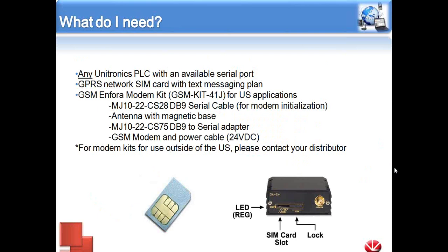So what do I need to do all this? This is going to work with actually any of our PLCs from the Jazz up. Jazz, M90, and all our Vision controllers support the modem. You do need an available serial port though. So if you're already using one serial port for a barcode reader or Modbus communication, you are going to need a second one.